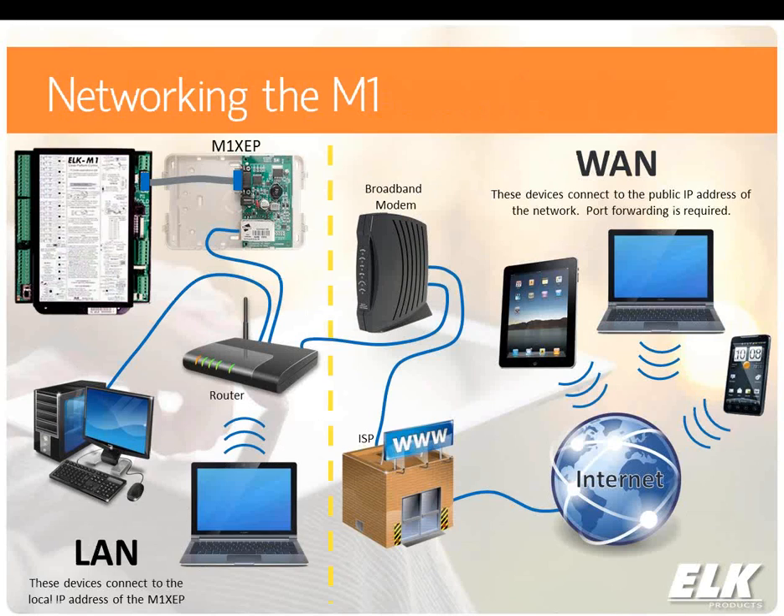This gives you an overview of networking the M1. The M1XEP connects to the main serial port and connects to your router. You can have devices on your local network — computers, Wi-Fi enabled tablets or phones — connect to the M1XEP using its local IP address. When you go outside the local network, which is what a lot of people are looking for to remotely control their system when they're away, you're going to be using the public IP address of that network. You'll need to do a port forward on the secure port of the M1XEP to allow those apps to work.